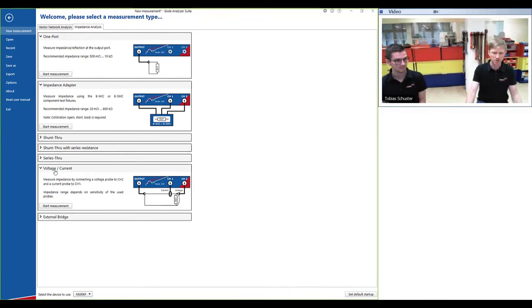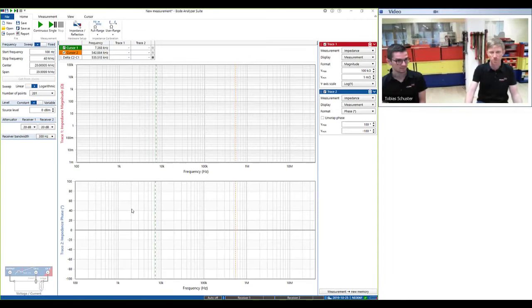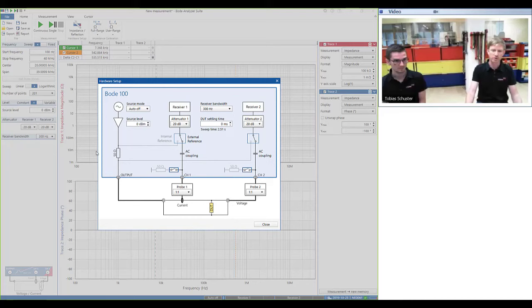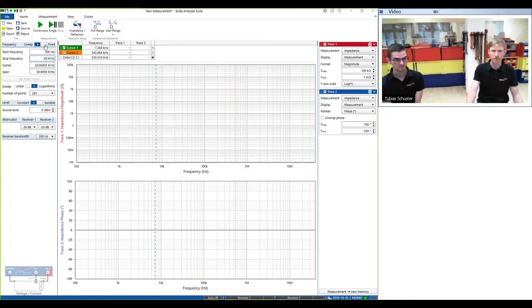And here we use the voltage divided by current method, where channel 1 receives a current signal and channel 2 receives a voltage signal. I'm going to discard the previous measurement. We don't need that anymore. And first, in the hardware setup, I have to configure channel 1 to have 50 ohm input impedance. That's a requirement from the current injector that delivers a 1 volt per amp signal at the monitor when terminated into 50 ohms. Then at channel 2, I selected 10-to-1 probe because we have connected a 10-to-1 probe. Then again, selecting the frequency range, we're going to measure again from 100 Hz to 10 MHz.